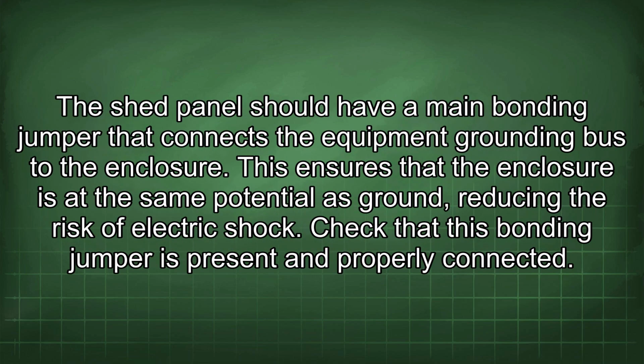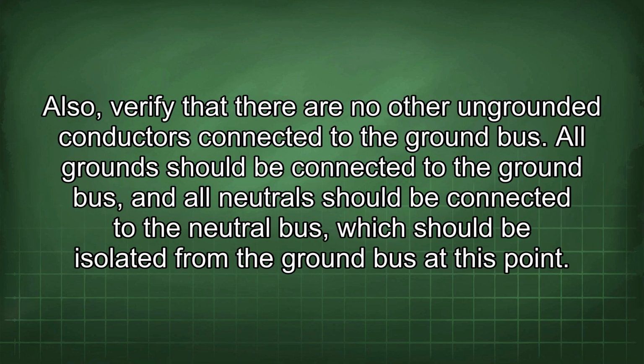The shed panel should have a main bonding jumper that connects the equipment grounding bus to the enclosure. This ensures that the enclosure is at the same potential as ground, reducing the risk of electric shock. Check that this bonding jumper is present and properly connected. Also, verify that there are no other ungrounded conductors connected to the ground bus. All ground should be connected to the ground bus, and all neutral should be connected to the neutral bus, which should be isolated from the ground bus at this point.